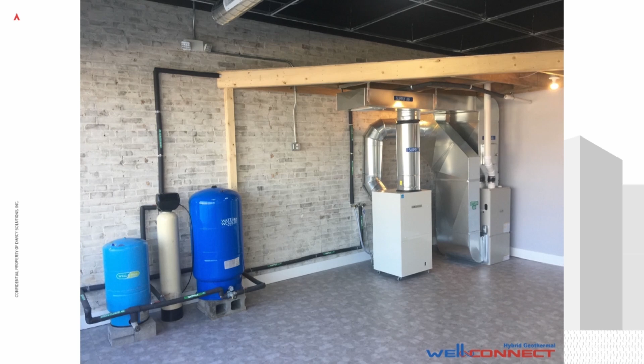Here's a typical install. To the far right here is an existing furnace. We set our unit right next to it. We tie in the supply and return ductwork. It's a 20 amp circuit, so these use about as much electricity as a hairdryer. We add an additional pressure tank because we want the pump cycle to be about a 10-minute cycle when the system is running, 2 minutes on to fill the tanks, 8 minutes resting. So a well pump's going to cycle about 140 times a day on a very cold day, where it's rated to cycle, say, 300 times. So we're working well within the capabilities of the well pump.